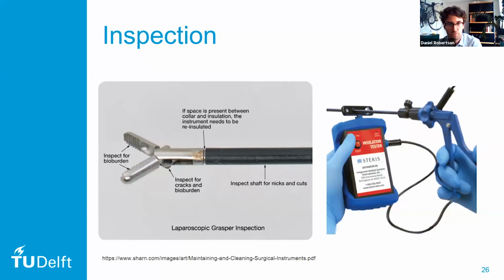So every instrument has to be inspected before it's disinfected or sterilized. Now, a few of the aspects you have to look for are bioburden in between the tip. You have to check to see if the mechanisms are clean. You have to check whether the mechanisms in the tip or in the hinges don't have cracks. And one of the most important things is we have to inspect the insulation on the shaft.